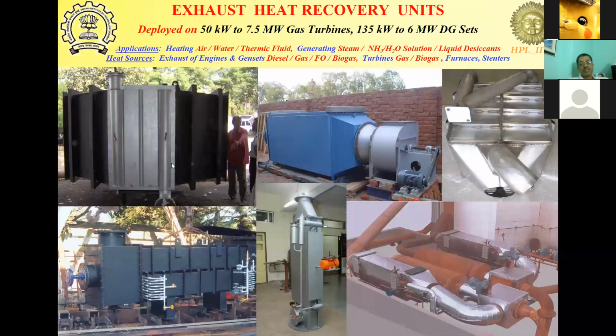Now, the conventional units were almost 3 times the size of our unit, which is 1/3 the capacity, 1/3 the size of a conventional gas turbine exhaust heat recovery unit. Gas turbine exhaust heat recovery is a simpler application if you see it that way, because the gas turbine exhaust has no contaminants in it. It's a clean gas. Although it's very hot, it is a clean gas. The temperature of the exhaust could be anywhere between 450 degrees to even higher, depending upon the type of gas turbine you're using.